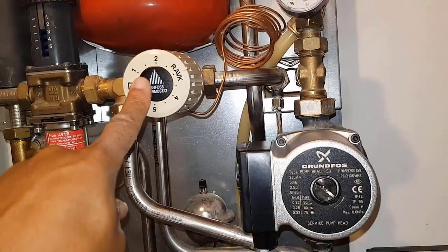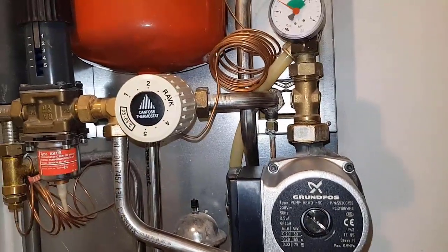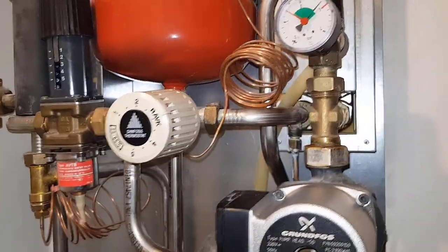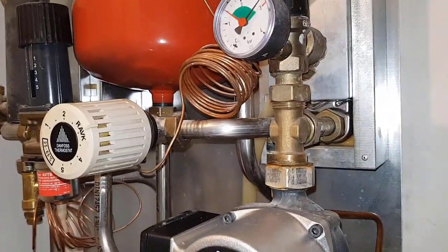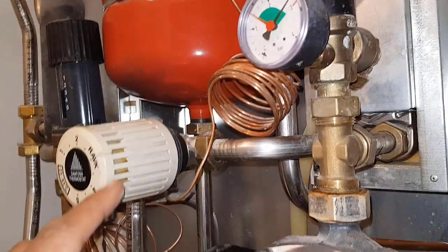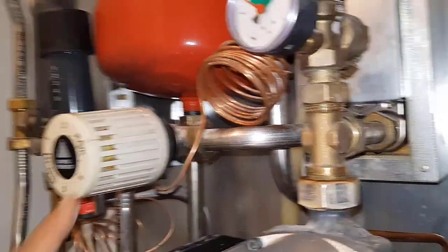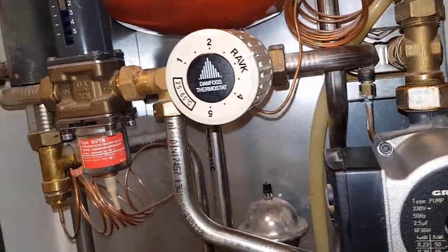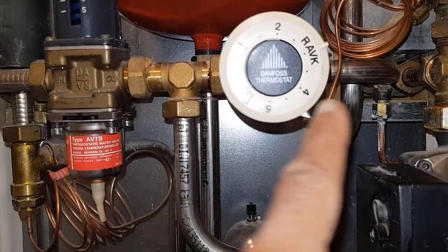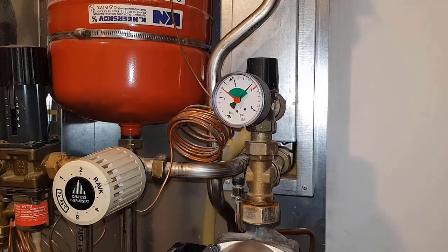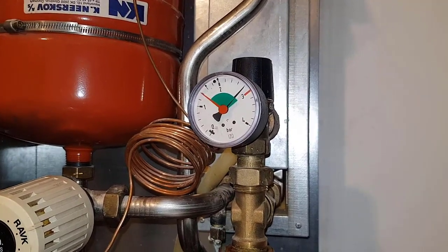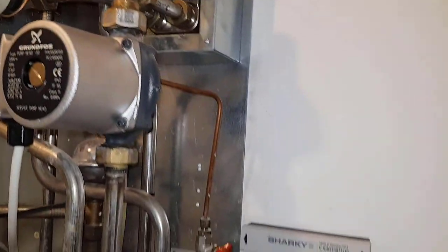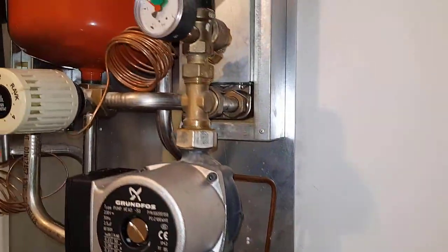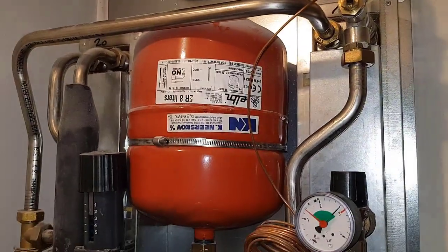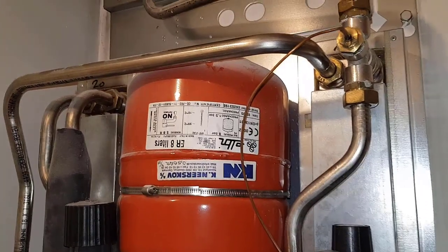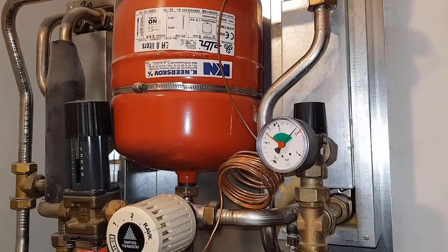So I've tried adjusting this thermostatic valve here, and there's no difference. So to me, the problem why the heat is not getting hot is that this is at fault, because as I said, we are getting flow this way but not that way. Incidentally, the pressure's gone right up to 3 because I opened this bypass, so it's allowed flow to go through. So I think this expansion vessel wants repressurizing as well, because it's increased in pressure quite rapidly.